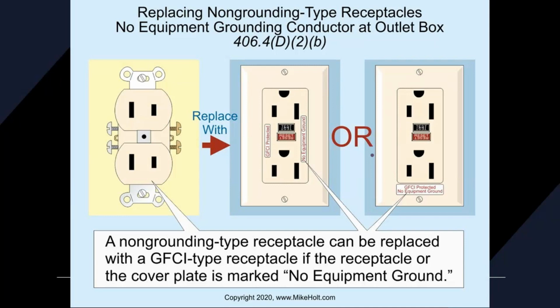All right, this is a hot one actually. Replacing non-grounding type receptacles. No equipment grounding conductor at outlet box. So in older houses, especially older Denver, older Aurora, older everywhere, non-grounding type receptacles can be replaced with a GFCI type receptacle if the receptacle or the cover plate is marked "no equipment ground." Okay?